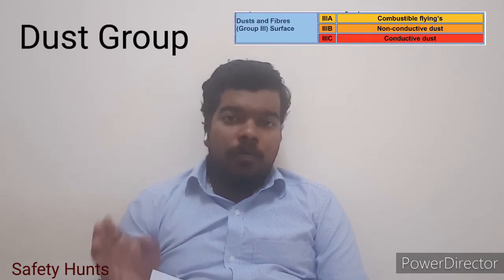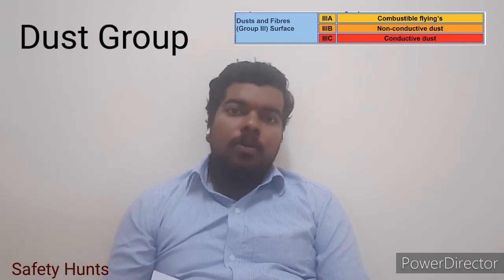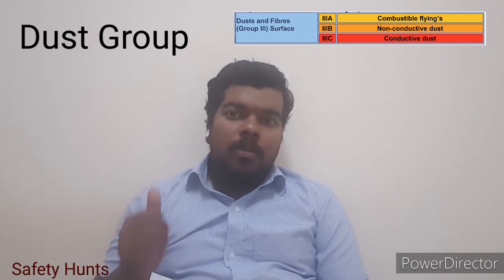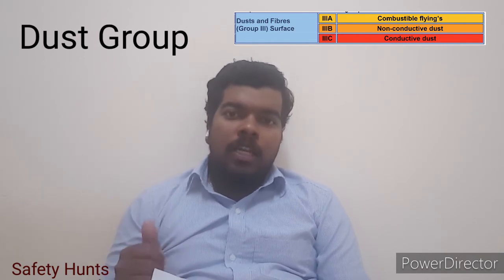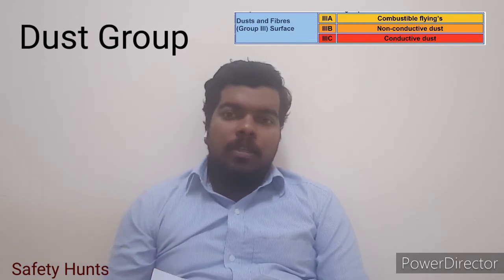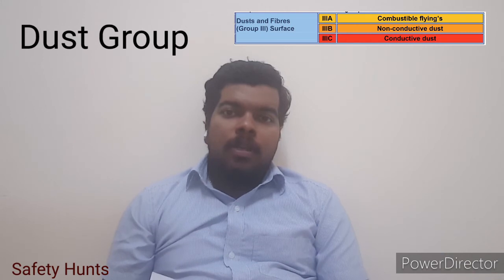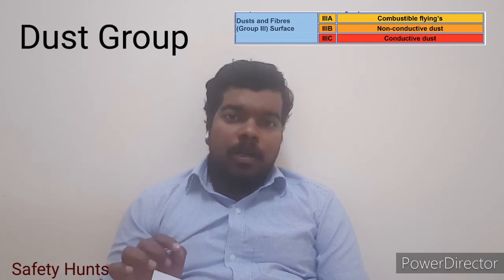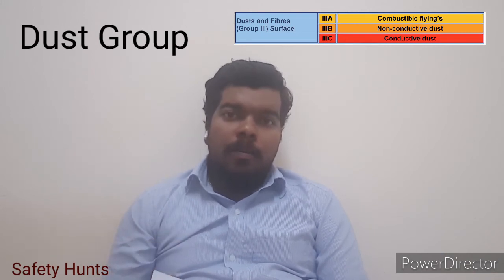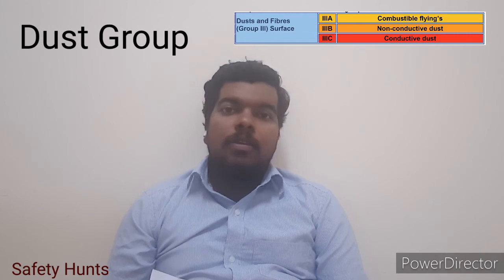Similarly, dust groups are also classified into three categories: 3A, 3B, and 3C. 3A means combustible dust, 3B is non-conductive dust, and 3C is conductive dust.